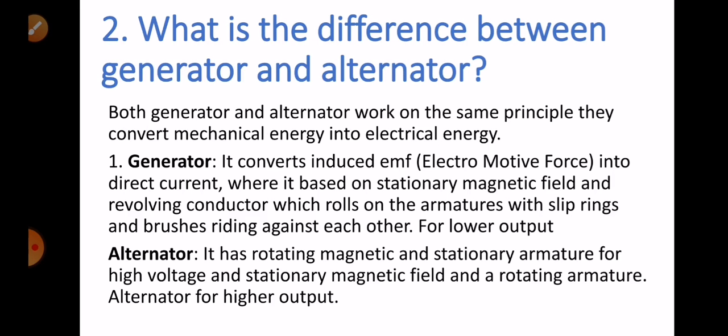Question number two: what is the difference between a generator and an alternator? Both work on the same principle — they convert mechanical energy into electrical energy. However, the generator converts induced EMF into direct current, based on a stationary magnetic field and revolving conductor on the armature with slip rings and brushes. This is used for lower output and lower voltage. The alternator uses a rotating magnetic field and stationary armature, and is normally used for high voltage or high output.